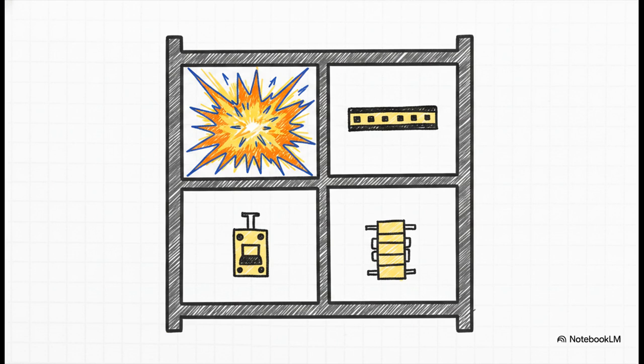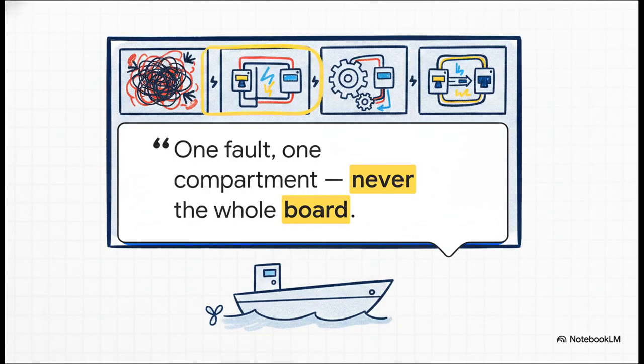Metal-clad switchgear is built using rigid steel partitions that physically separate the different internal zones. So if a fault, like a massive, explosive arc flash, happens in one zone, it's completely physically isolated from the rest of the cabinet. Which leads to the golden rule of this design: one fault, one compartment, never the whole board. It's a structural philosophy that basically expects the worst to happen. It's designed so that a catastrophic fault can blow up in one specific area without taking down the entire switchboard. Because if you lose the whole board, you're leaving the vessel completely dead in the water. Not exactly a good day at sea.